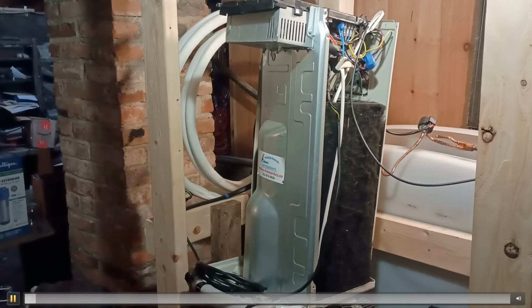Now, my worst case day is quite a bit more. Assuming a 0 degree Fahrenheit day, where the heating average temperature for January in my location is 25 degrees Fahrenheit, the worst case day is 0 degrees Fahrenheit. So now we're talking 23,000 BTUs per hour, 22,000 BTUs per hour.